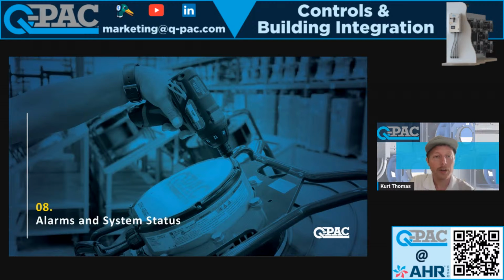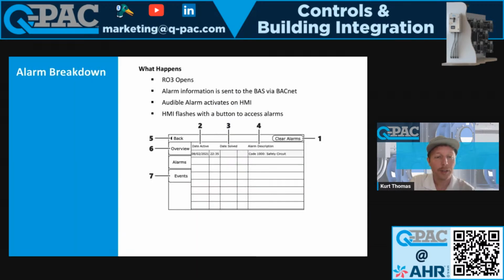All right, alarms and system status. So what happens whenever you have an alarm? There are 4 things that happen really. RO3, that relay number 3 opens. So that's a binary output that says, hey, something's wrong. It doesn't tell you exactly what's wrong, but it gives you an indicator that you have an error somewhere in the system. The second thing that happens is alarm information is sent to the BAS via BACnet.